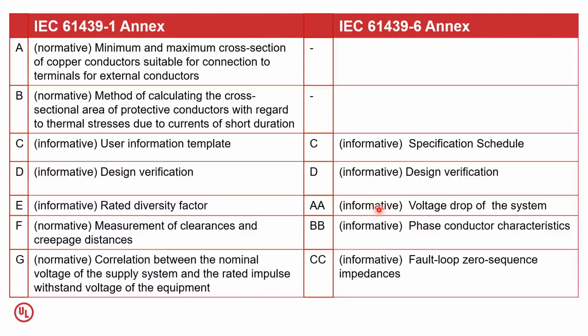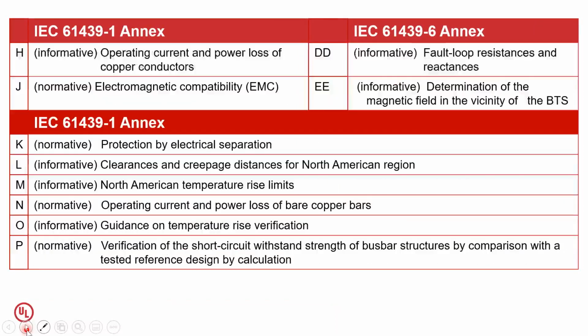Then you have a couple of other annexes which are essentially informative: the voltage drop of the system, the phase conductor characteristics, and the fault loop zero sequence impedance. The reason this is informative is that the end user will dictate if they want any of these verifications for their busways. Let's look at a couple more annexes. As you can see here, Annex H is again informative because it talks about the operating current and power loss of conductors. But then Annex J is made normative.